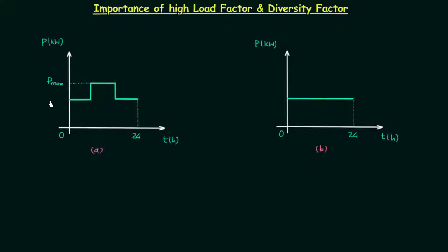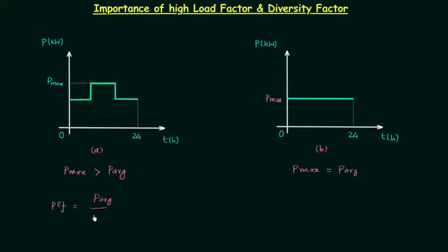In load curve A, P_max is the maximum power demand. If you see the load curve you will find the maximum power demand P_max is greater than the average power demand. The plant load factor is equal to average power over the maximum power demand, and from here we can say that the plant load factor is less than unity — less than 100 percent.